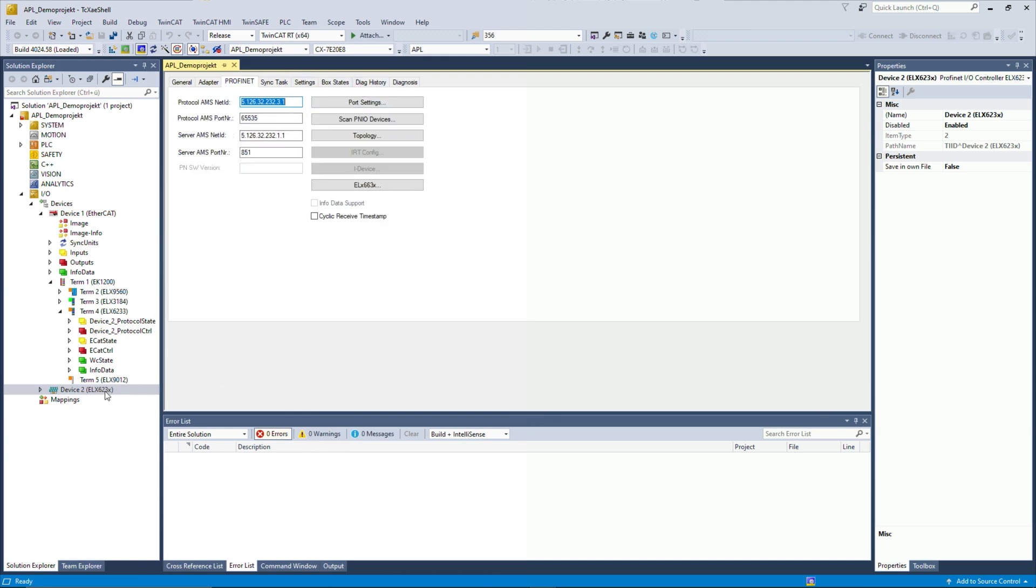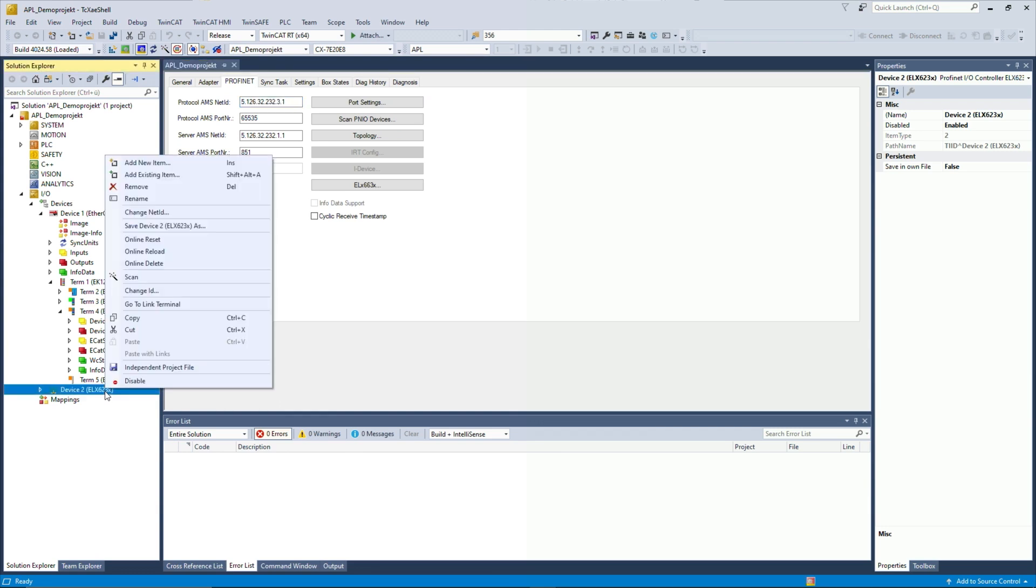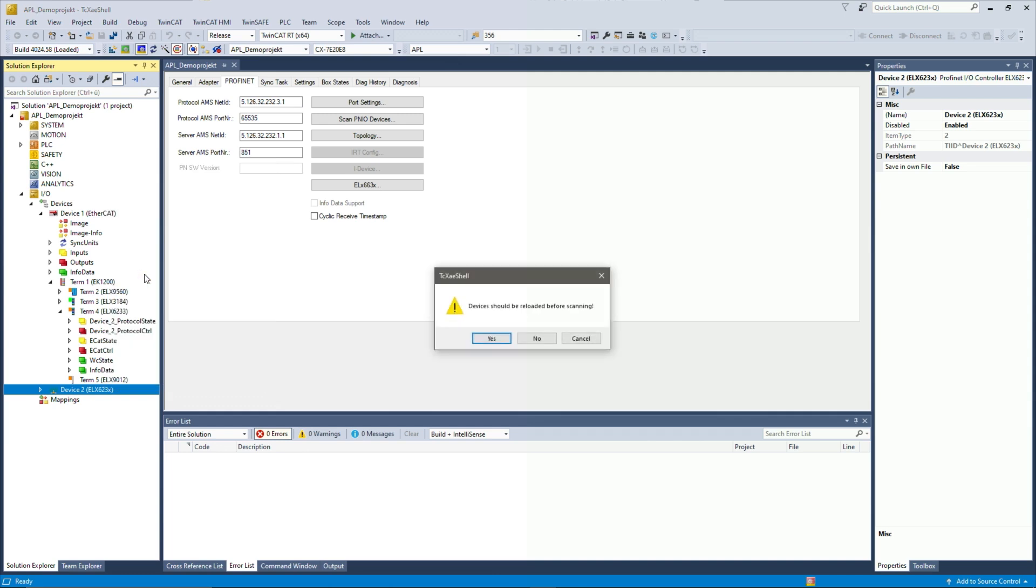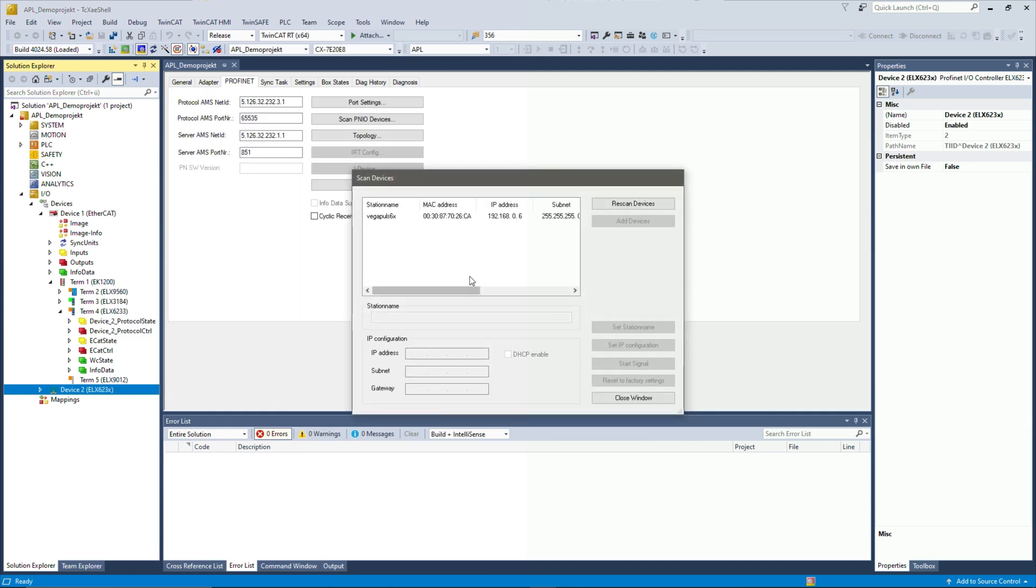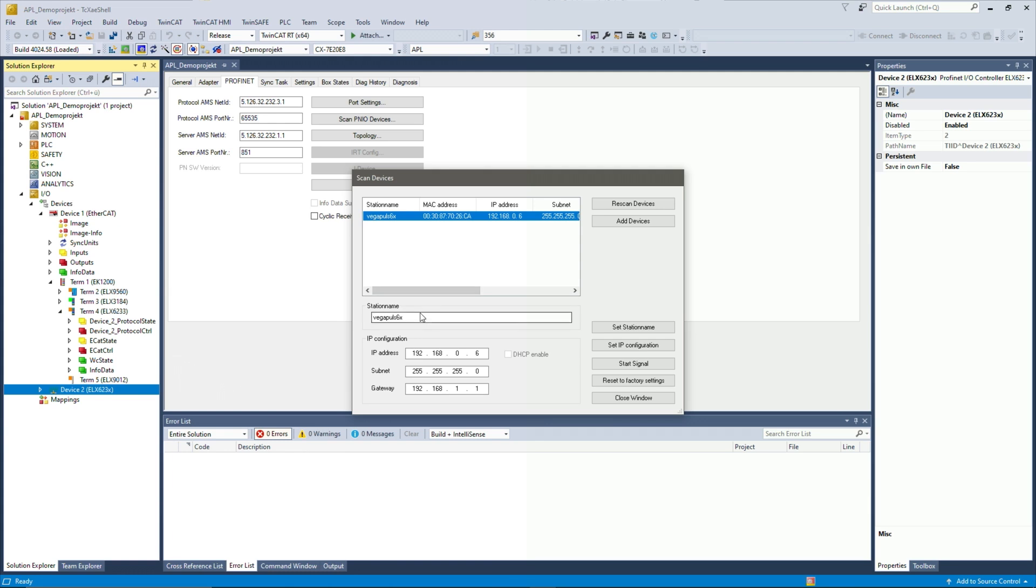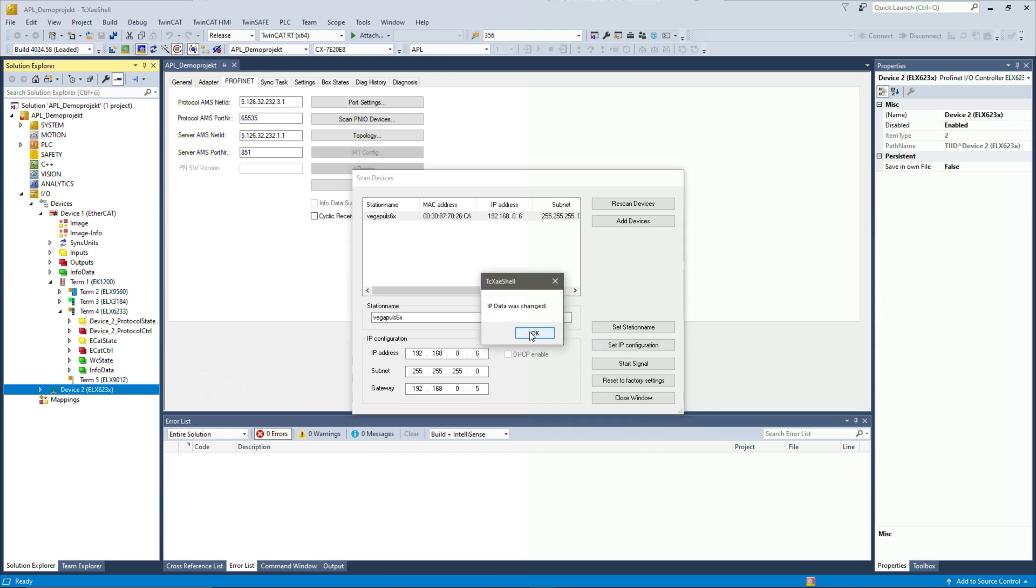The next step would be to scan the connected field devices, so even the APL sensor itself. Let's press right click again and scan. And after that, we see this window here where we can already see we have a Vegapuls 6X connected, which is a radar sensor for level detection. We can change the gateway now to 0.5 as we did before and the IP address is already in the right network. Then we can set the IP configuration.